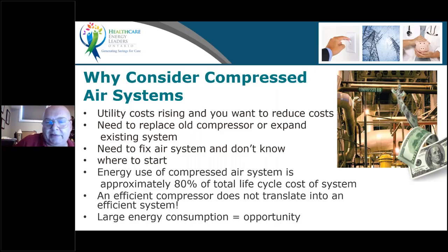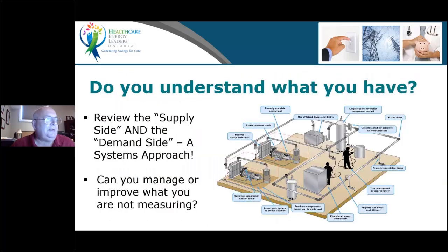And I think that's one of the things I've found over the last 15, 20 years with the introduction of VFD compressors, that once customers install these particular makes and models, they believe the system is working at peak efficiency. And in fact, they've left a lot of energy waste and money on the table, and I usually go in there and find what needs to be done properly before ever replacing compressors. Obviously, the larger the system, the more complex, the larger the opportunity when it comes to savings.